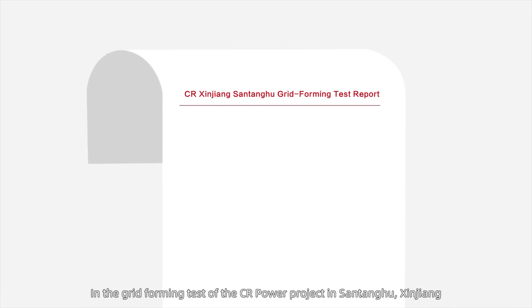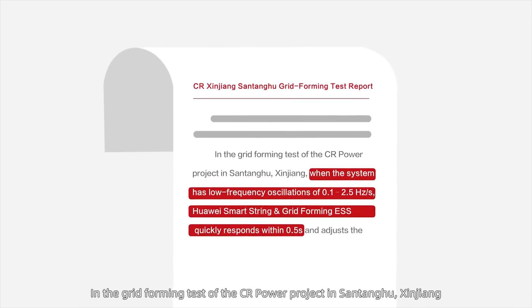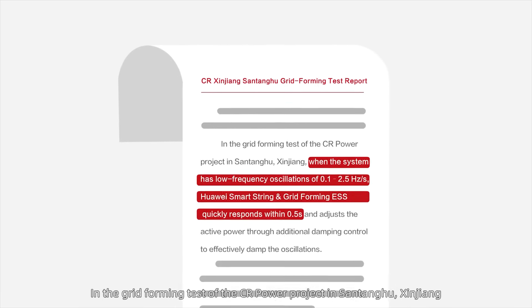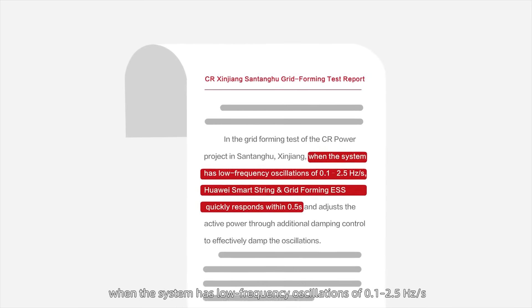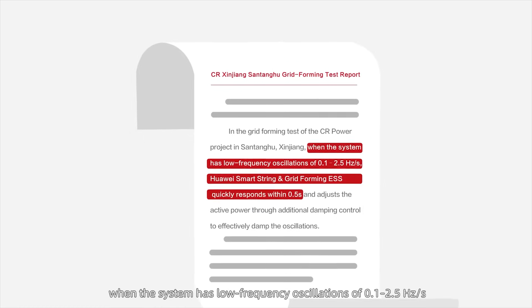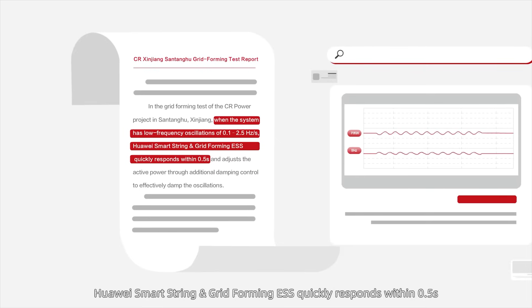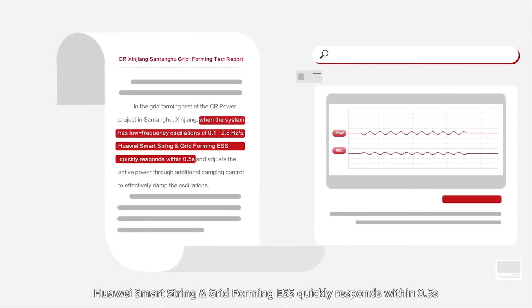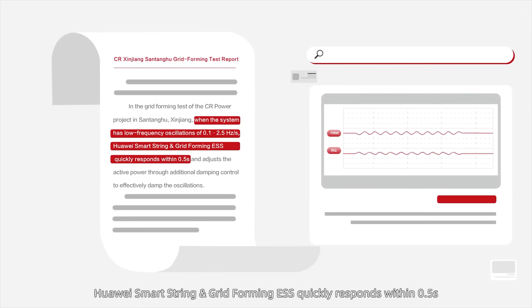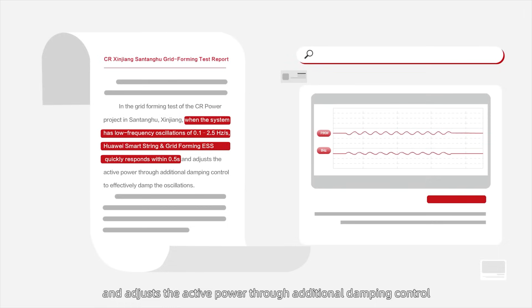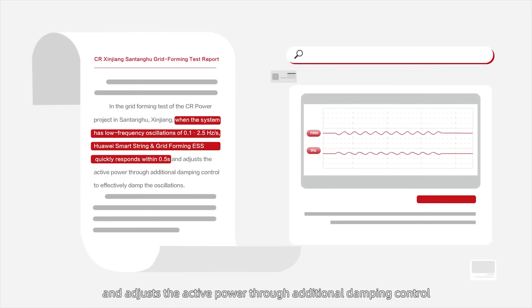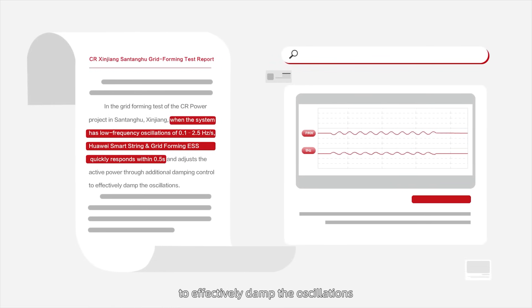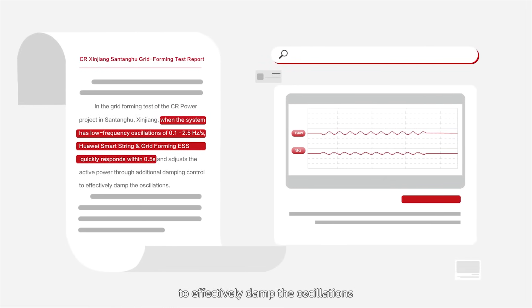In the grid-forming test of the CR Power Project in Santanghu, Xinjiang, when the system has low-frequency oscillations of 0.1 to 2.5 Hz per second, Huawei SmartString and Gridforming ESS quickly responds within 0.5 seconds and adjusts the active power through additional damping control to effectively damp the oscillations.